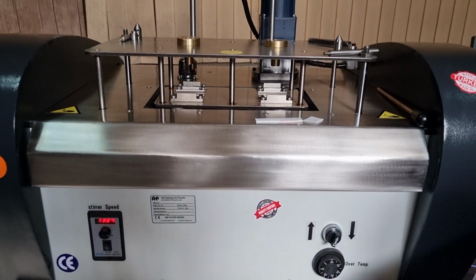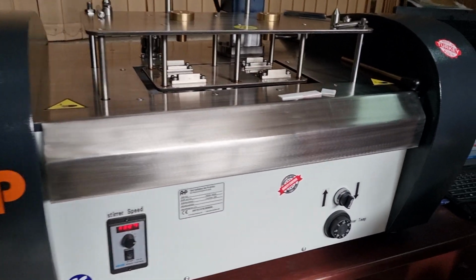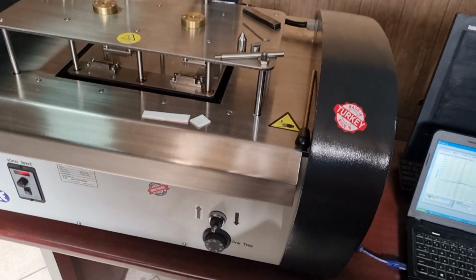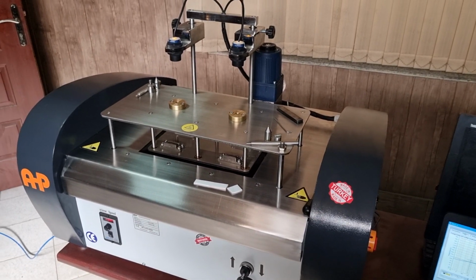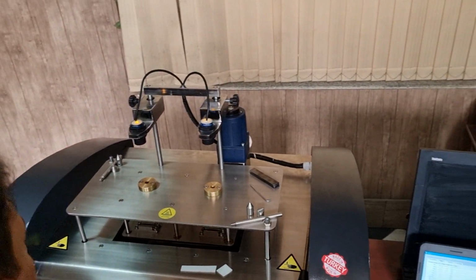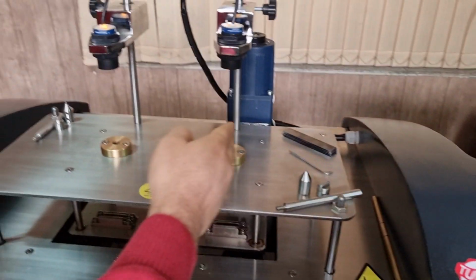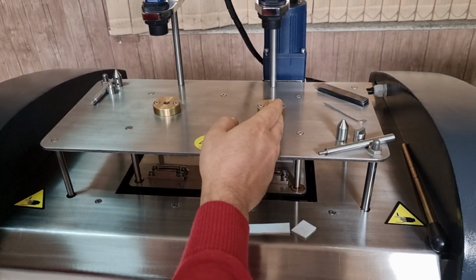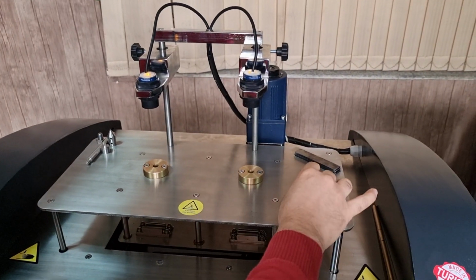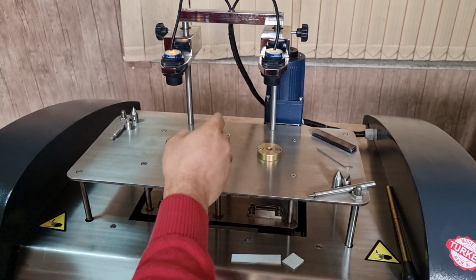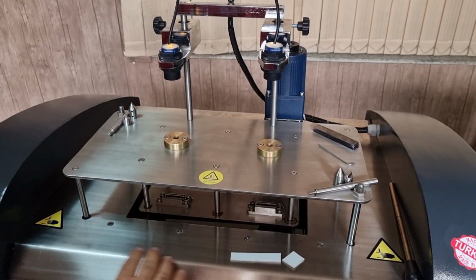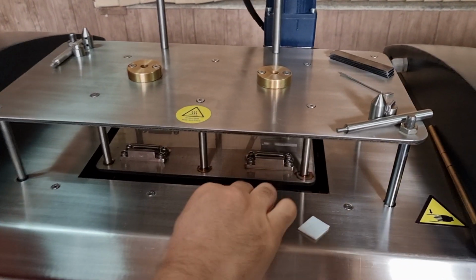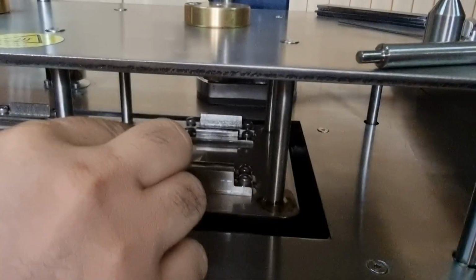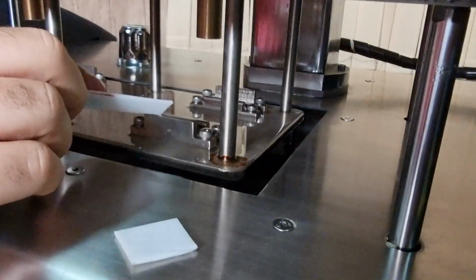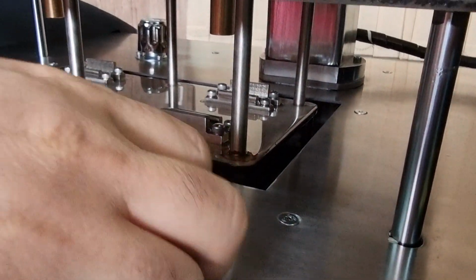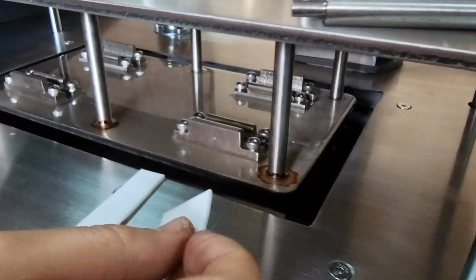I'm briefly presenting the Vicat HDT testing machine from AHP Plastik Makina. The machine includes the carrier for samples. The number of stations will be according to the customer request. Sensors for reading the displacement. The resolution for reading the displacement is 0.001 millimeter. The sample placement fixtures: two stations for HDT, heat deflection temperature, and the middle point is for placing the sample for Vicat testing.